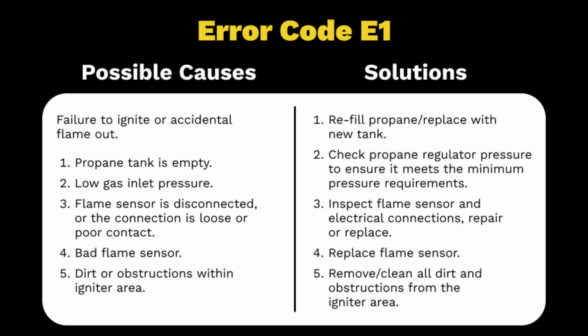If an error code E1 presents, this signifies a failure to ignite or an accidental flameout. Environmental conditions like wind can cause this. Ensure that the propane tank is not empty and meets the minimum pressure requirements of 13 inches of water column pressure.